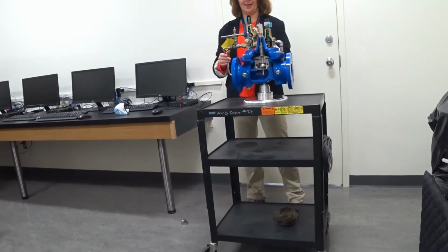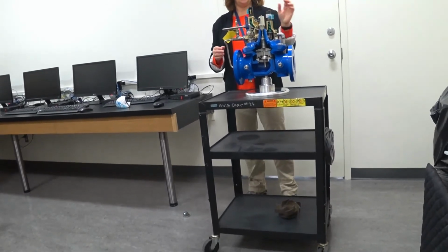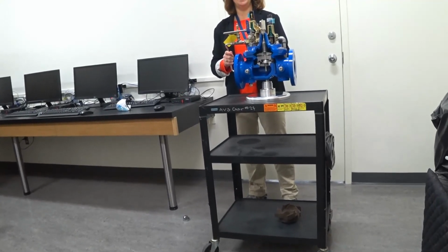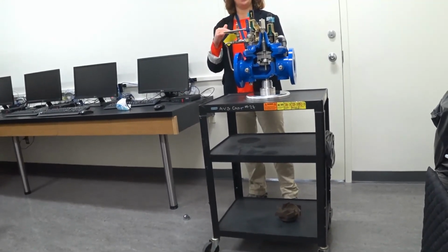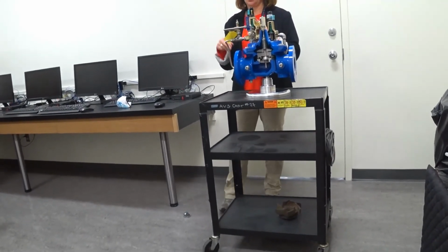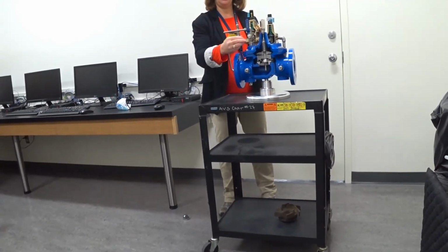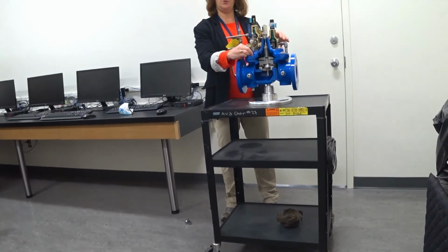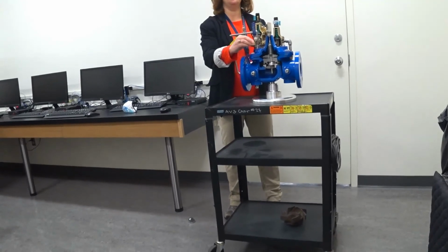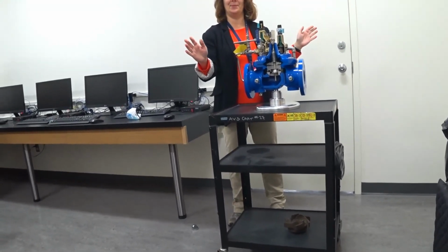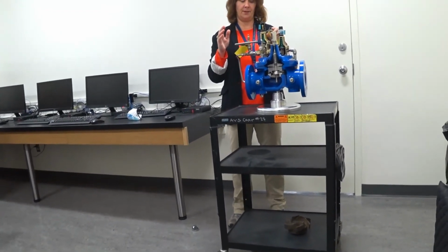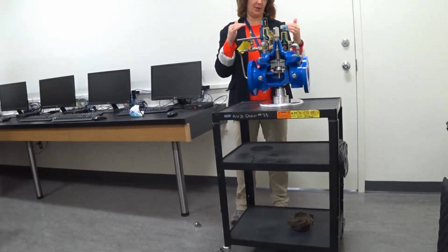Okay. And so, again, I haven't talked about this in a minute. This all just keeps functioning along until your upstream pressure drops. If your upstream pressure drops because of a main break or whatever happens, this valve will start to close. When this valve closes, all that water is diverted onto the main valve, which closes this valve. And so this valve could be wide open, saying, I want this valve to be wide open too, but if this one's closed, nothing else happens. Okay?